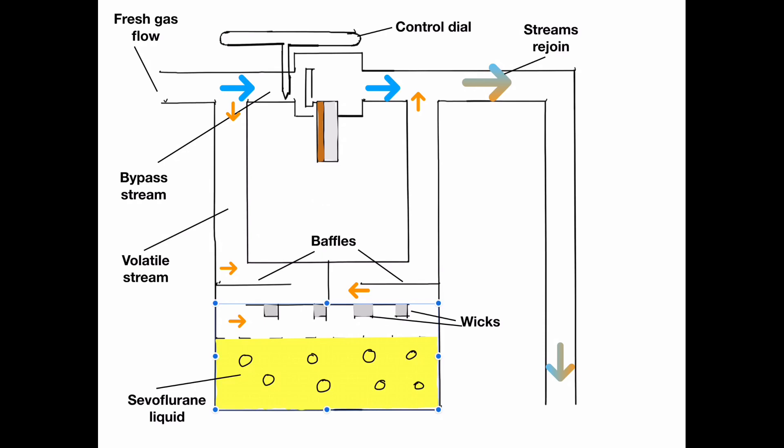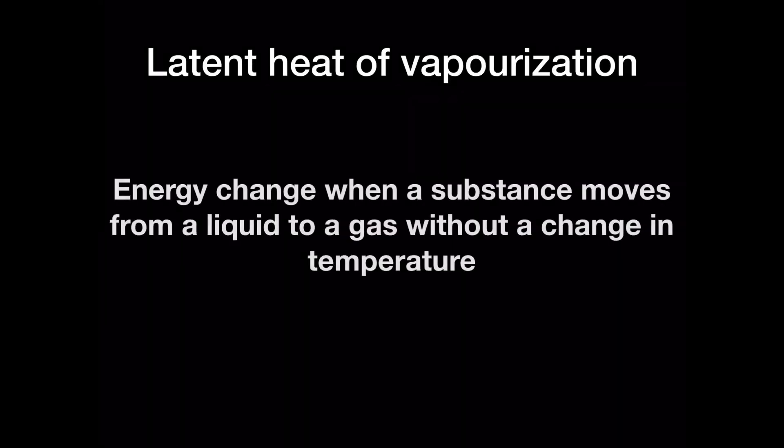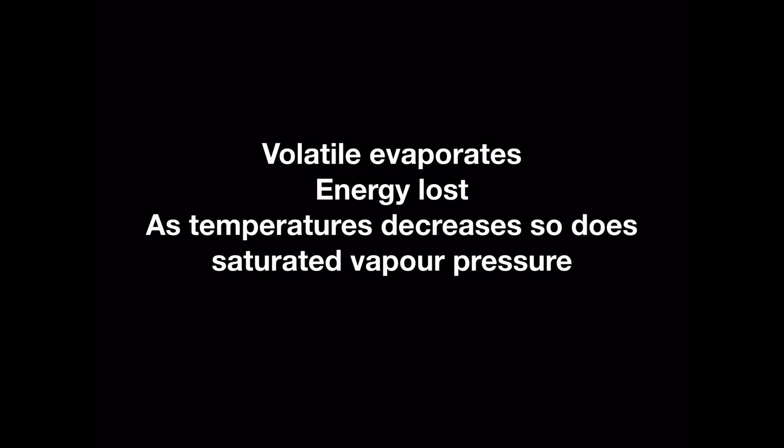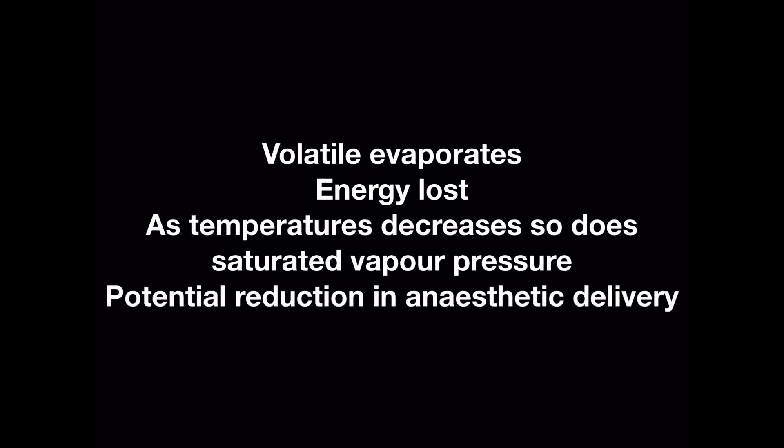If the gas from the volatile stream was not fully saturated with anaesthetic vapor, then there would be no way to control the amount of volatile anaesthetic delivered to the patient, and therefore this mechanism is crucial to the safe supply of anaesthetic agent. Due to the principle of the latent heat of vaporization, as the volatile liquid evaporates, it loses energy, causing cooling of the remaining contents. Given that the saturated vapor pressure exerted is reliant on temperature, as the temperature decreases, so does the saturated vapor pressure of the volatile, meaning the output of the vaporizer will be reduced.